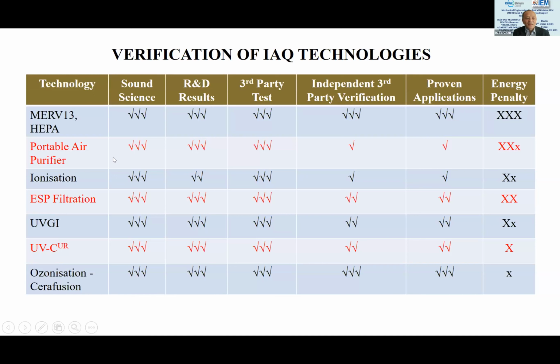Next, portable air purifiers: 3 ticks for science, since most use HEPA filters; 3 ticks for R&D; 3 ticks for third-party test; but independent evaluation only a single tick because of efficacy concerns, and proven application a single tick since they are very localized. Energy penalty is less than MERV filters since this is ventilation at source — you don't push air throughout the whole ducting system.